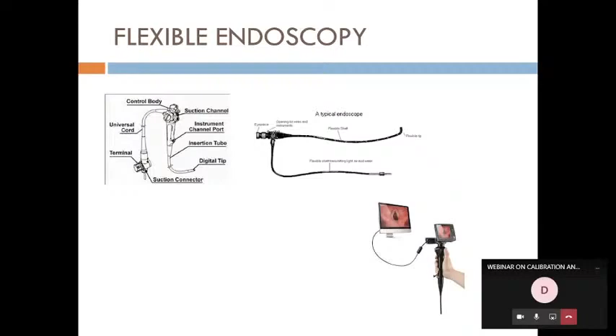So we need to check the leak test first. The only thing is we can leak test the scope as we do for our two-wheeler tires. The same way we can check the leakage in the scope. In case any channel has been damaged, the fluid or air will enter into another channel. So where the leakage is coming from can be checked with a leakage tester in the scope. The problem we face is scope leakage.